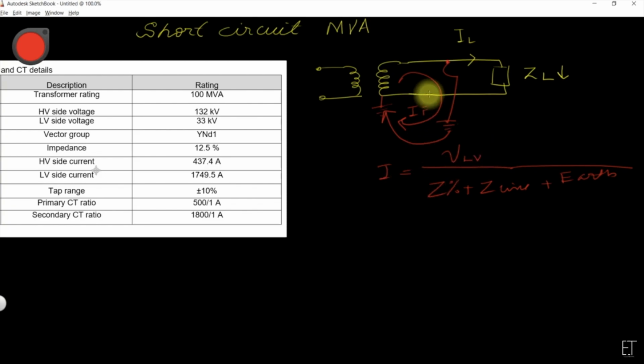But what will happen if there is a short circuit on the terminal? This is the worst case of the short circuit, when there is a short circuit on the three-phase terminal of the transformer, so all three phases of the terminal are short-circuited. The current will flow through all three phases, and the only thing limiting the current here is the impedance of the transformer itself. We can call this the percentage impedance, and here you can see it is 12.5 in this transformer.